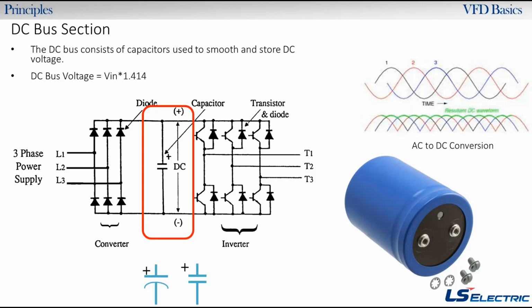Another thing to keep in mind is some people don't understand why their DC bus voltage is so high. Your DC bus voltage is actually the input voltage times the square root of 2, or Vin times 1.414. So if you have a 480 volt input drive, that voltage could jump all the way up to 680 volts at idle if you plug that into the calculation. And then a 230 volt drive is going to be around 320 volts or so at idle. And when I say at idle, that means with no load or maybe a light load, that's what your voltage will be around.